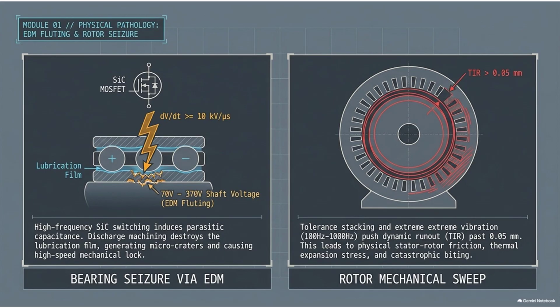Now, if there is a slight manufacturing error, say the layers of laminated steel on the rotor stack up just slightly crooked, the center of mass is thrown off. Right, yeah. The rotor starts to vibrate. If the speed of the motor hits a resonant frequency, those vibrations amplify wildly. So now you have a heavy, hot, expanding piece of metal wobbling at 1,000 hertz. And it just eats up whatever is left of that tiny little air gap. It physically scrapes against the inside of the stator. It sweeps the inner wall. And the moment that spinning rotor touches the stationary stator, the friction is unimaginable. It just catches. It bites down into the copper coil windings, snapping them instantly, and you have a violent, catastrophic mechanical seizure. Sledgehammer is definitely the right word for that.